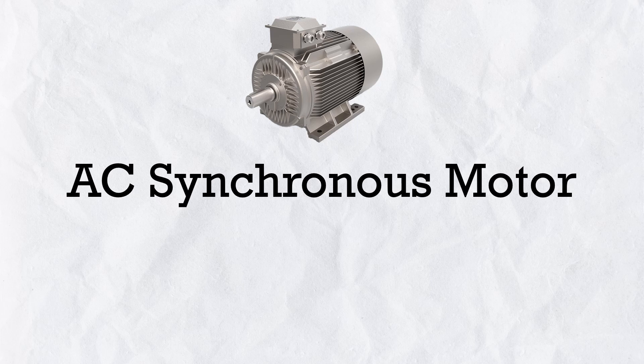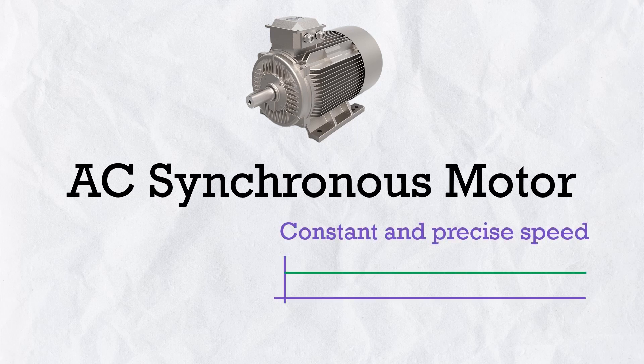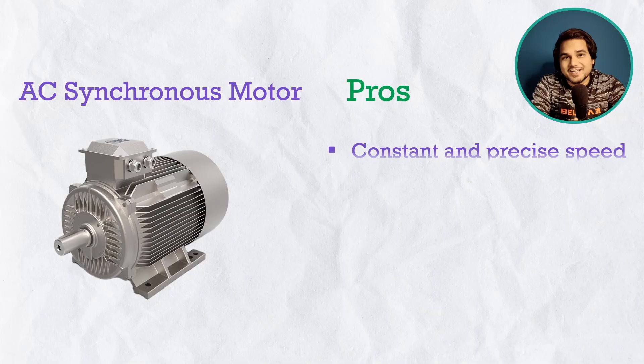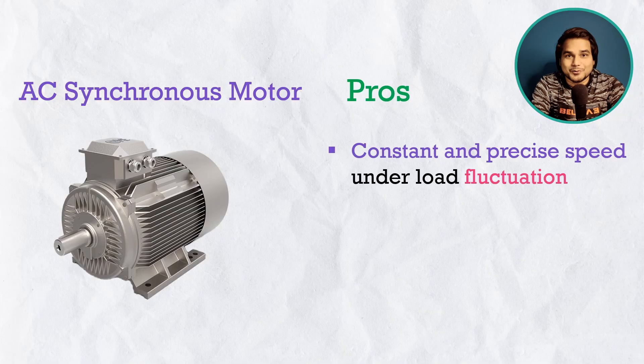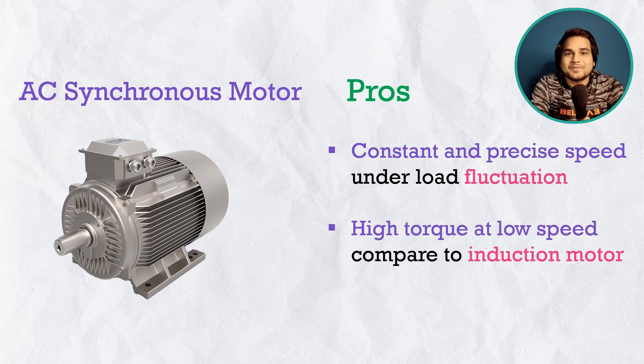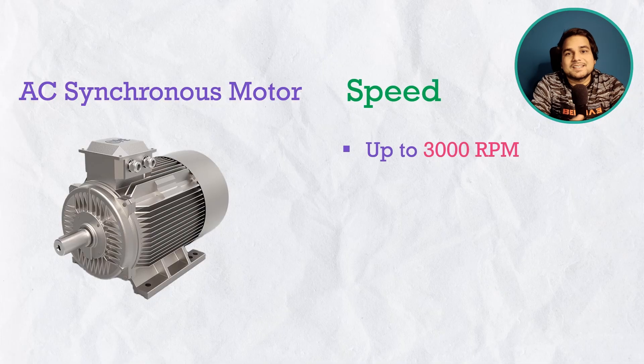To overcome the load-dependent speed problem, we move to the AC synchronous motor. Its main advantage is fixed, precise speed regardless of load fluctuations. AC synchronous motors can also provide higher torque at low speed compared to AC induction motors. They are used where fixed, precise speed is needed. Maximum speed is the same as induction motors — up to 3000 RPM — but overall torque capacity is lower, though more constant.